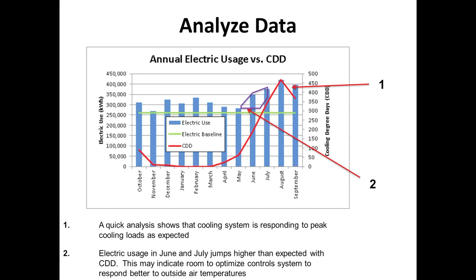And there's an accurate amount of energy consumption that's used, which means that the building is actually sized pretty correctly, most likely, and the building system peaked and used the most energy at the time when outside temperatures were the warmest. What's interesting is if you follow that arrow from number 2 up, I drew a little purple trapezoid. We see that there's a big jump in electricity usage as the building reaches into the summer. This usually tells us that there's some type of control issue, that maybe the building's not reset for outside temperatures. Maybe cooling was initiated before it was necessary. Maybe the building doesn't use economizers. But there is some issue there that we should explore further.